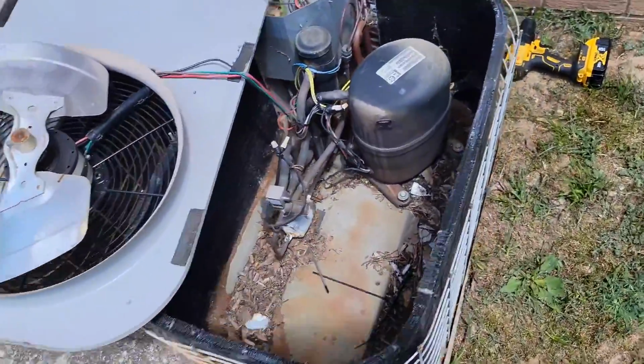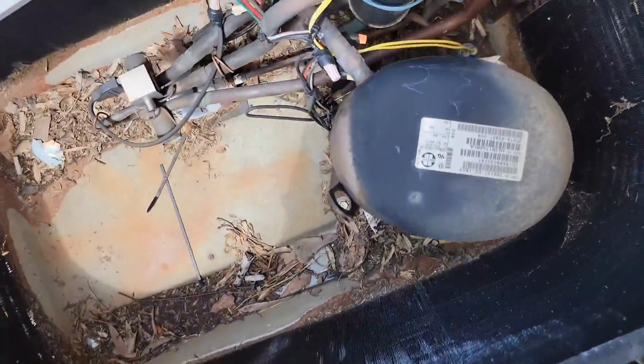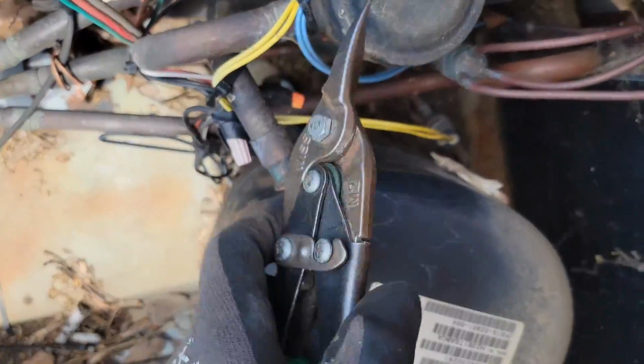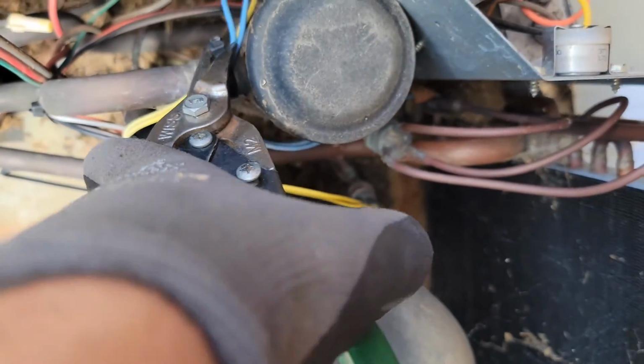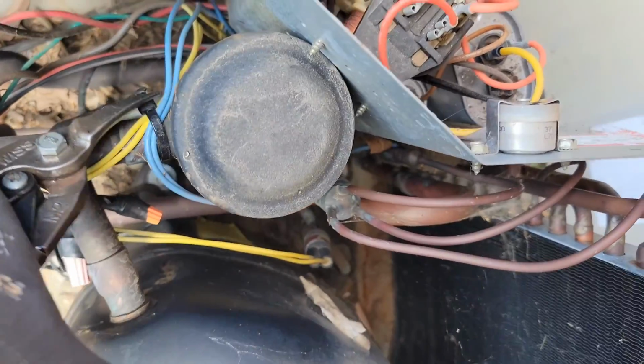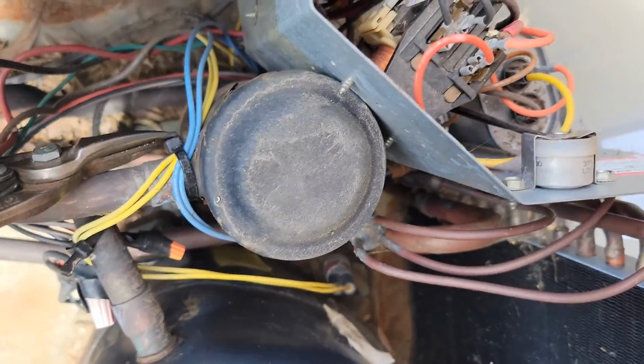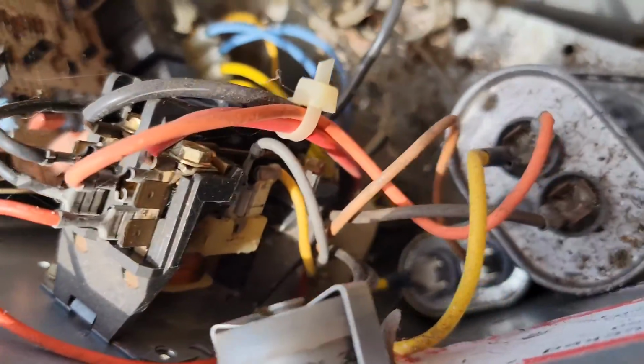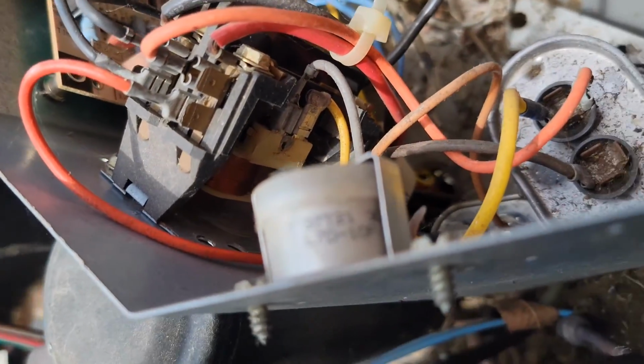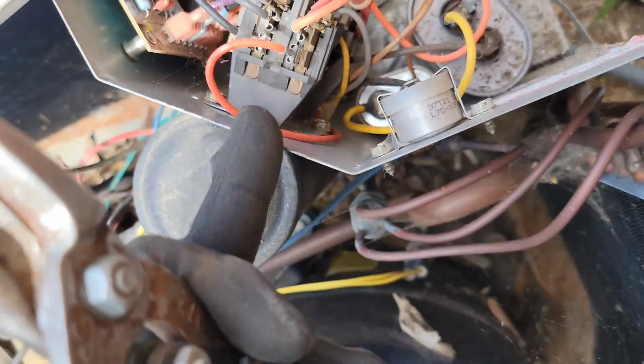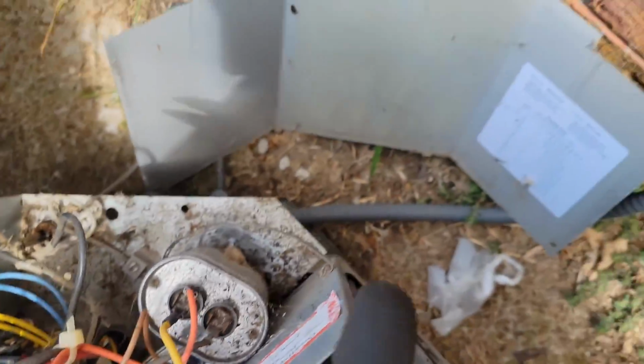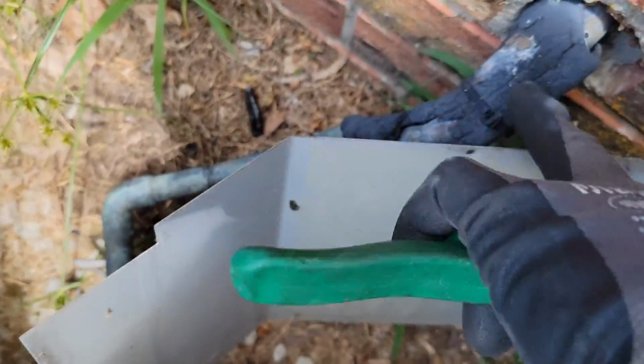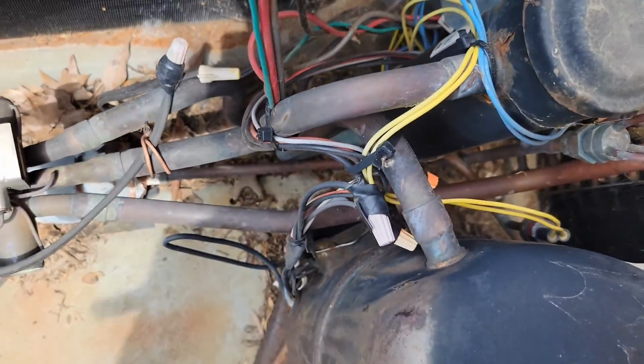So I got the whole top off the unit. And what am I gonna do? I am going to cut every zip tie where there is a wire, and I'm gonna find that short. And when I find that short, because I've already looked at the coil, contactor coil's right there, you can see. Doesn't look burnt. We got that coil there. We got our thermostat wire with this splice. That could be it. But we got a bunch of wire touchings.